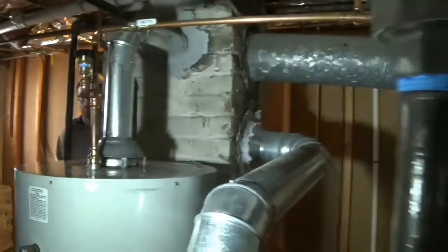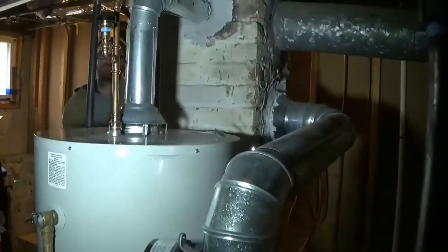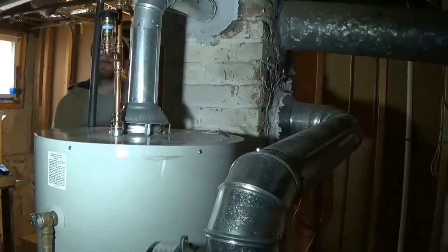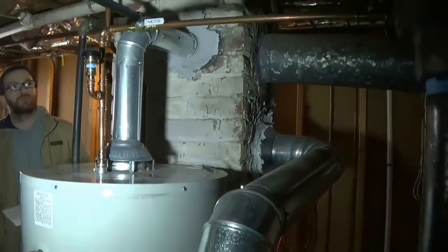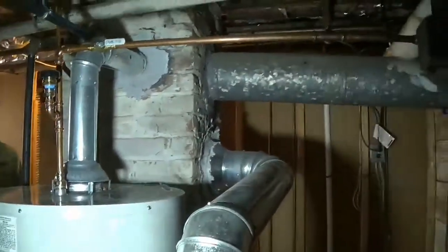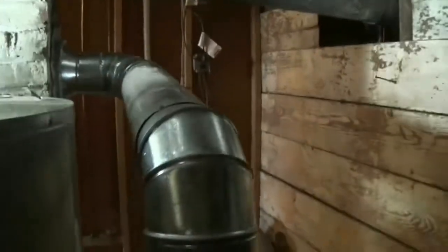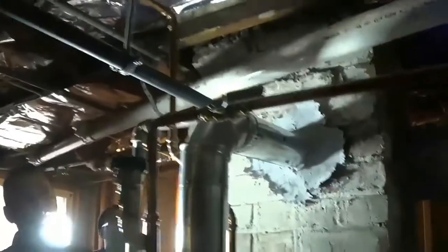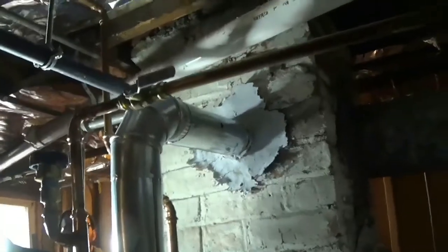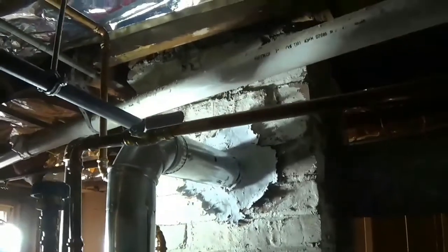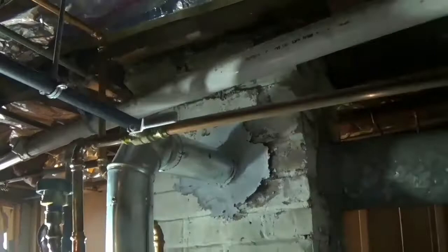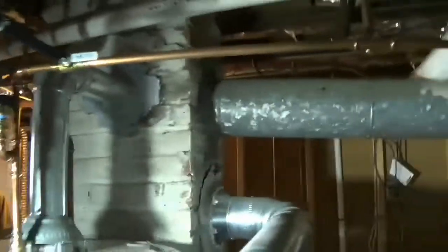Another thing we look at when we get into a combustion appliance zone is how the flue connectors are sloped, if there's enough upward slope. The boiler has a really good slope. This has a pretty good slope. It needs to be a minimum of 1/4 inch of rise for every foot of run. So this probably just meets that. This a little one, tight, right? Yeah, this one definitely meets it. All right, so we make a note about the condition of venting, and it's good.